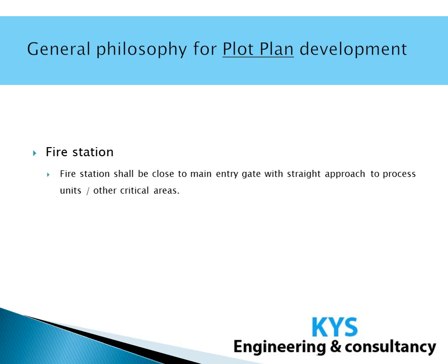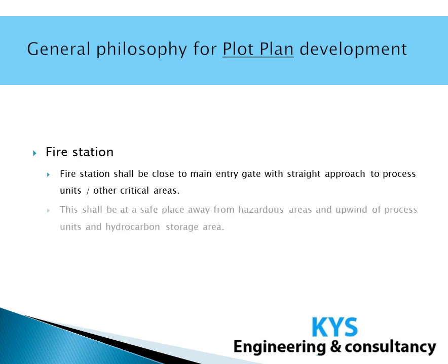Fire station. Fire station shall be close to the main entry gate with straight approach to the process units and other critical areas. Also, it shall be located in such a way that it is away from the hazardous area and upwind of the process units and hydrocarbon storage area, so that if there is any leakage in the process units or hydrocarbon storage area, the gases shall not travel to the fire station.